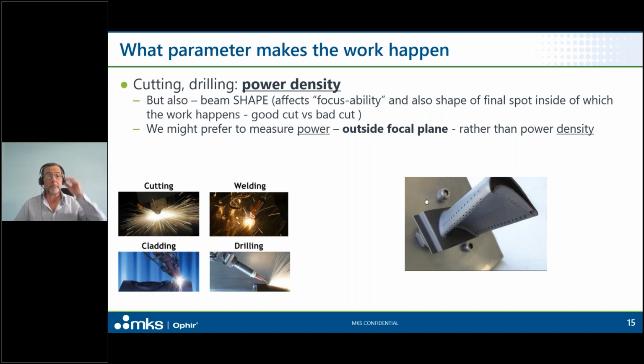We might prefer, rather than measuring power density in the focal spot, to measure just the total power. And we're going to want to do that, by the way, outside the focal plane, because inside the focal plane, I might cut, weld, or drill my measurement device. It's the same number of watts and joules outside focus as in focus, right? Keep that in mind. So I might prefer to measure power rather than power density. It's easier, and assuming that we know, and this is a big assumption, exactly what the beam shape in the focal spot will be, measuring the total power in the beam might give me enough information to tell me what I need to know.